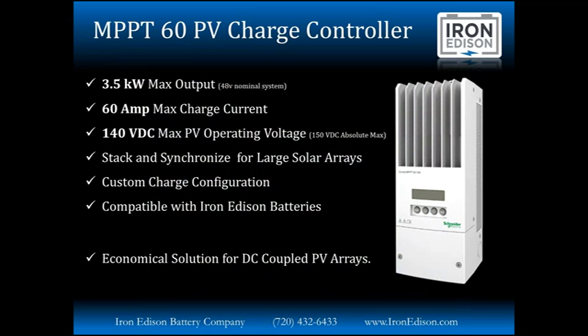controller. MPPT is maximum power point tracking. This is a breakthrough technology about 10 years ago that is a digitally controlled step-down transformer. So the original system design called for using 12-volt solar panels hooked almost directly to a 12-volt battery. The MPPT, or maximum power point tracking technology, allows us to attach a higher voltage DC solar array to a charge controller, and then through a very efficient 95 to 98% efficient transformer, we can step down that high voltage input to exactly match the battery voltage.